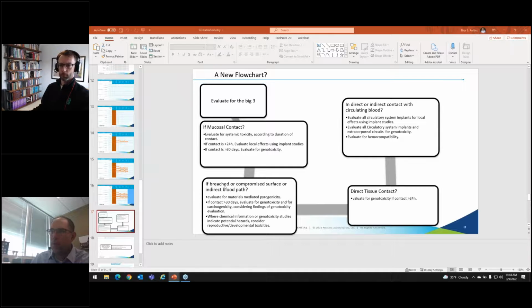If it's not mucosal, but if it's breached or compromised surface with indirect blood, then you need to evaluate for material-mediated pyrogenicity. If that contacts greater than 30 days, then you evaluate for genotox, carcinogenicity, and also the findings of that genotoxicity to see how the carcinogenicity may work. And then if you do need to do genotoxicity, maybe you do chemical characterization to look at those other hazards like reproductive toxicity. If you have direct tissue contact, you need to evaluate for genotoxicity plus the other things.